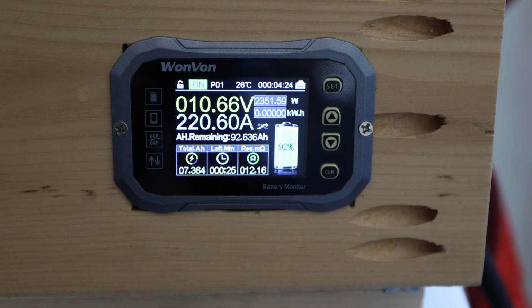It does not have an overcurrent protection, at least not configured properly for the recommended maximum discharge current of 100 amp.